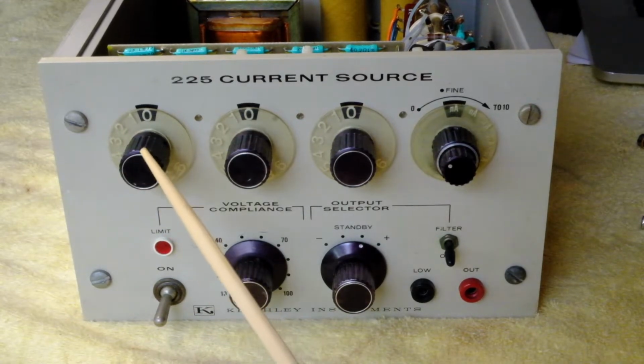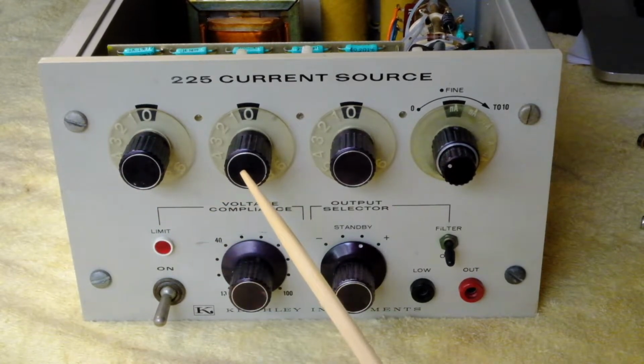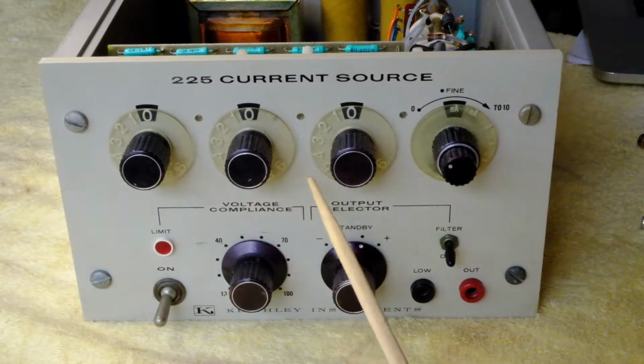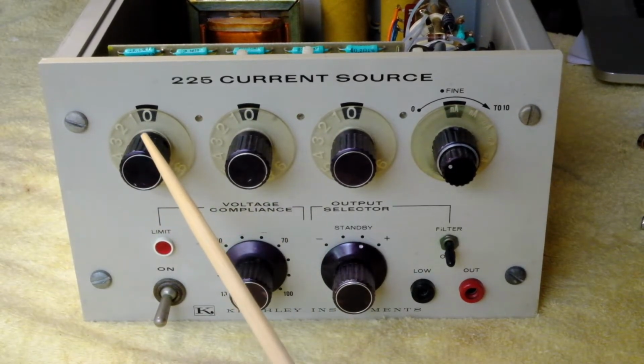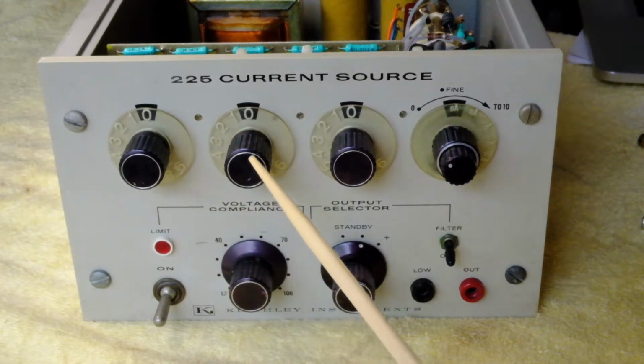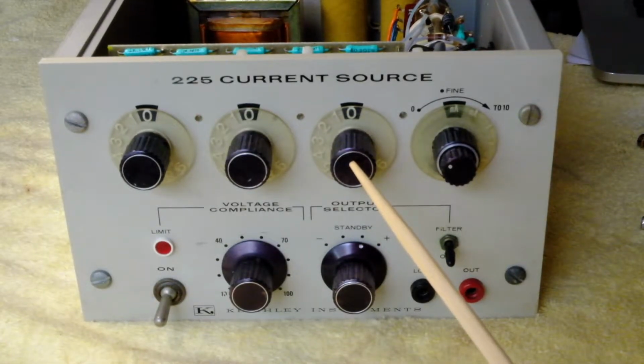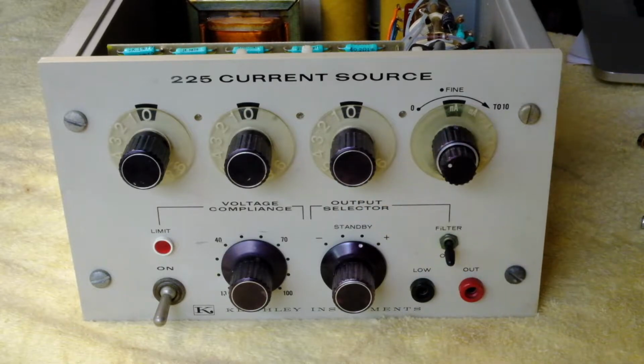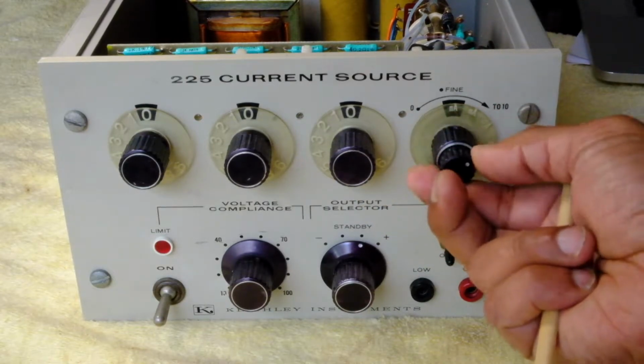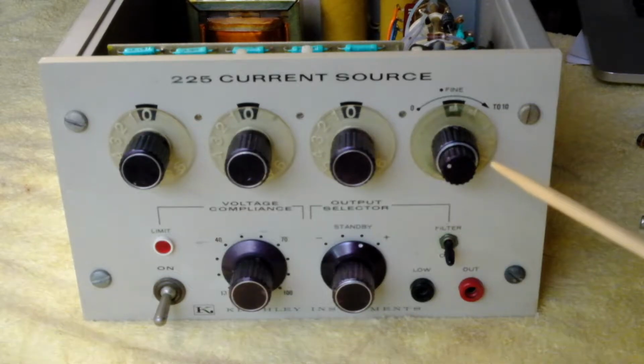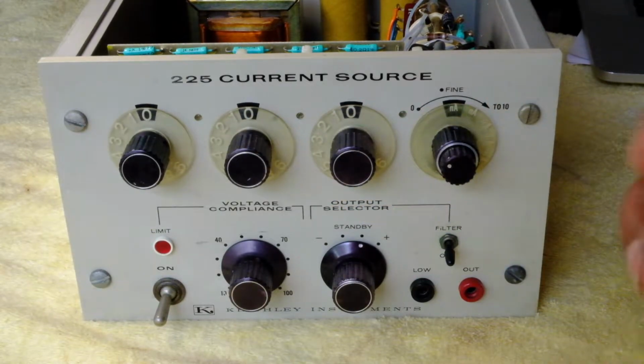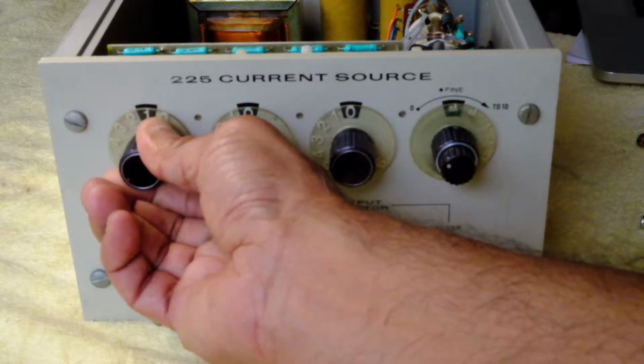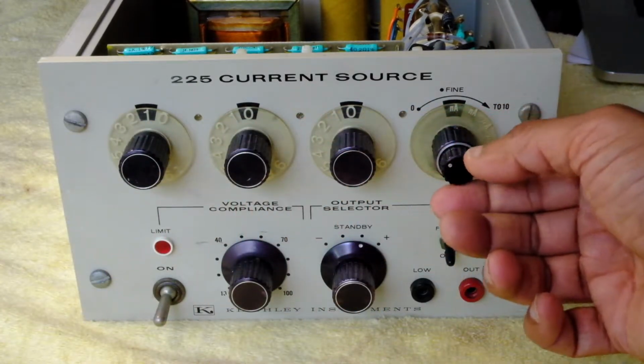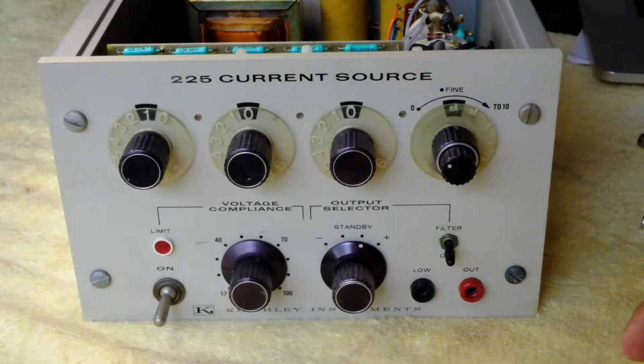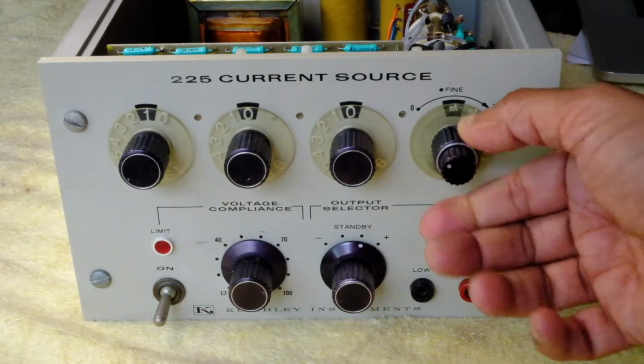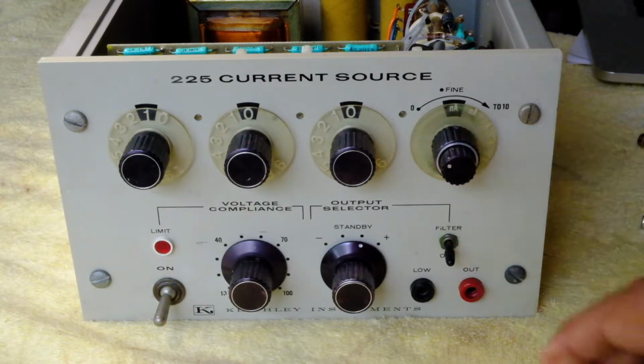And then you have the 3 decade resistance decade settings. The most significant digit is here on the MSB, and then the middle and the LSB, the lowest significant digit. And you also have a fine control here in this knob, which is 0.02% of the full scale. So if you have a full scale reading of, let's say, 100, you can adjust this by 0.02% of that. Normally I keep it on the leftmost side, so this is at 0 position right now.